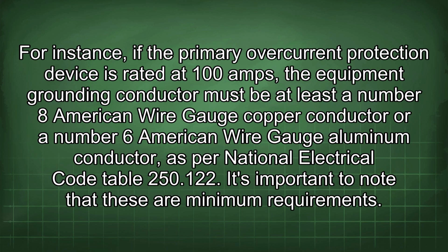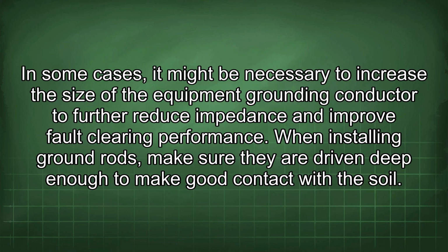For instance, if the primary overcurrent protection device is rated at 100 amps, the equipment grounding conductor must be at least a number 8 American wire gauge copper conductor or a number 6 American wire gauge aluminum conductor, as per National Electrical Code Table 250.122. It's important to note that these are minimum requirements. In some cases, it might be necessary to increase the size of the equipment grounding conductor to further reduce impedance and improve fault clearing performance.